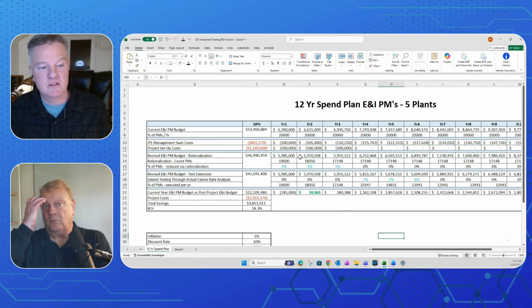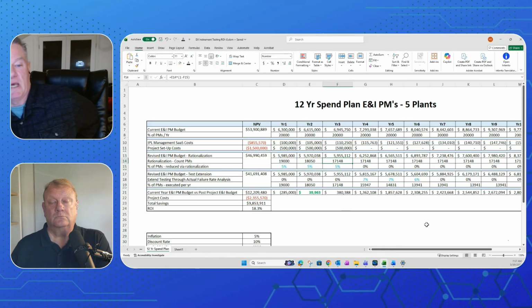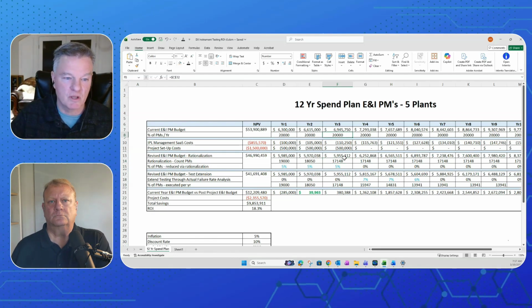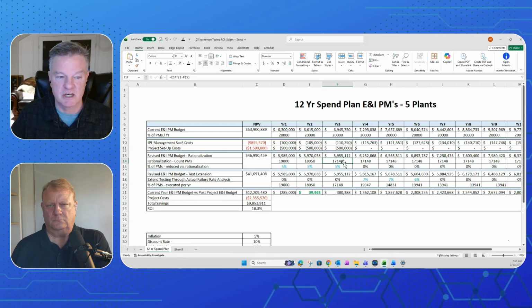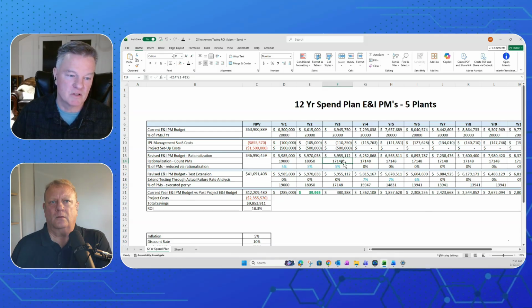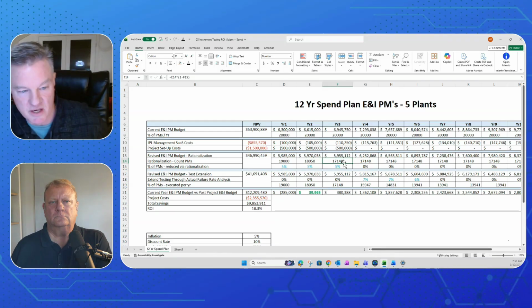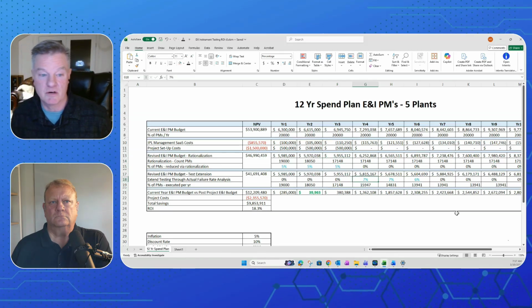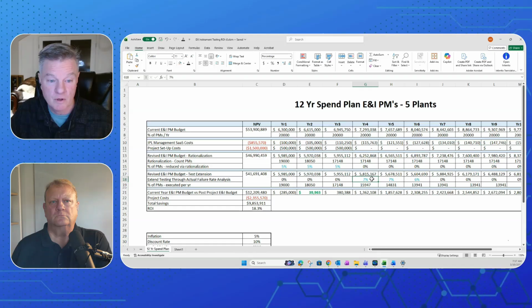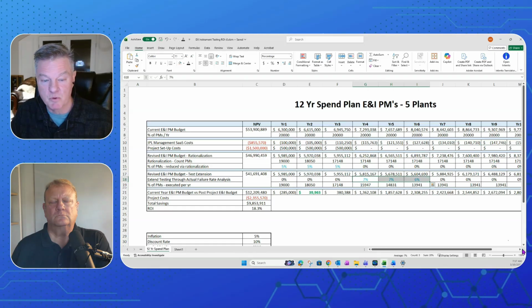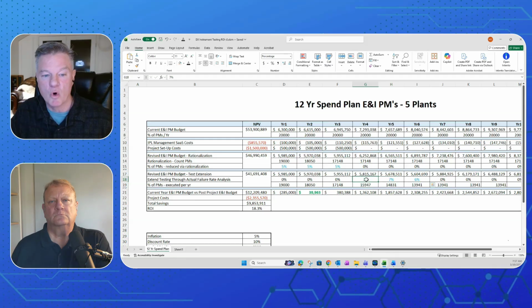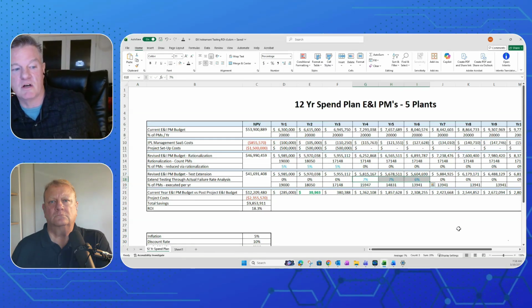Yeah. So I'm knocking my annual PMs down to 17,148 versus 20,000 just by going through the rationalization exercise, writing my approved vendors list program, rationalizing what we test today. And now it's saying we don't have statistically valid data. This is a very conservative assumption until year 4. And in years 4, 5, and 6, we're going to yank some stuff out, and that was magically 20%. So we're going to be able to only extend testing on 20% of the stuff.